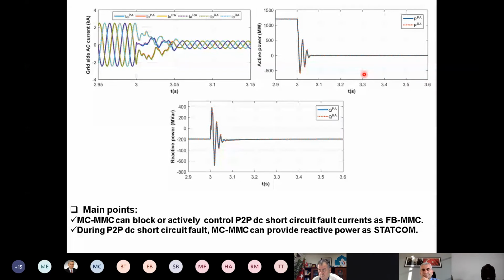This is why we drop the active power to 0, while we return to the rated reactive power as it was in normal conditions, with grid current still controlled. So the main point here: the mixed cell MMC can block or actively control pole-to-pole DC faults like a full bridge MMC, and also during a pole-to-pole DC fault, the mixed cell MMC can provide reactive power, as shown here, as a STATCOM.